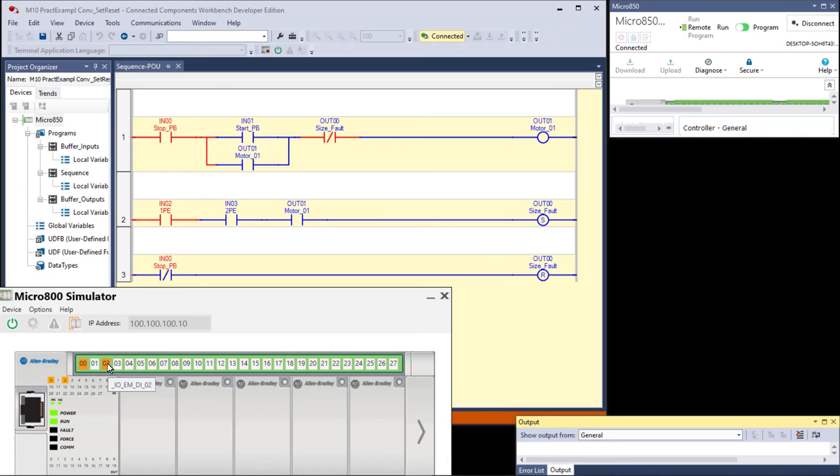Now, someone can put their hand in front of the photo eye. However, if we're running cartons, we're going to double-click 1. That starts the conveyor, and then we're going to see something pop into photo eye 1. If it's a regular size carton, the correct one, photo eye 1 will lose that obstacle before photo eye 2 picks it up. And then if the motor keeps on running, then it clears photo eye 2, and out it goes onto the next conveyor.